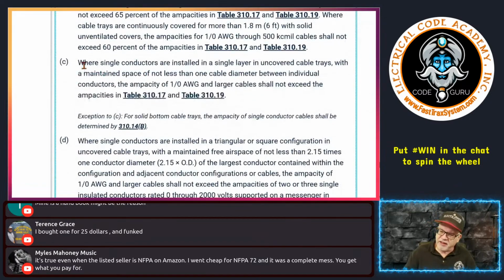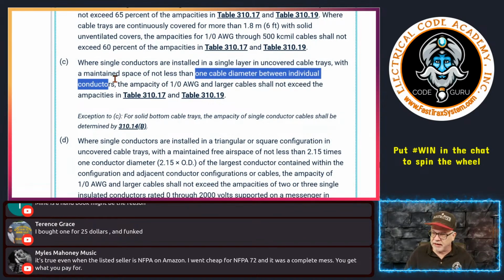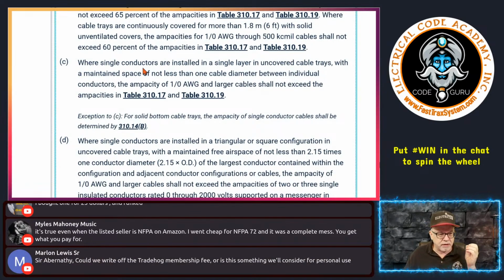So next one, how about C? C says single conductors are installed in a single layer. So you're just putting conductors in there, single layer, in an uncovered cable tray, with a maintained spacing of not less than 1 cable diameter between individual conductors. So this is what's the problem with the code right now, guys, and I'm going to do my best to fix this by 2029. Look at this one statement. It says single conductors in a single layer, then it says maintains not less than 1 cable diameter. So it talks about using single conductor, and then it talks about it being a cable. Then it turns around and says between individual conductors.